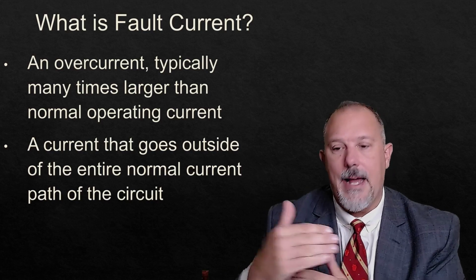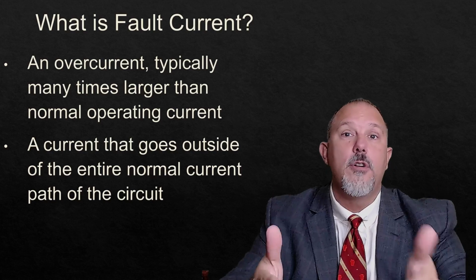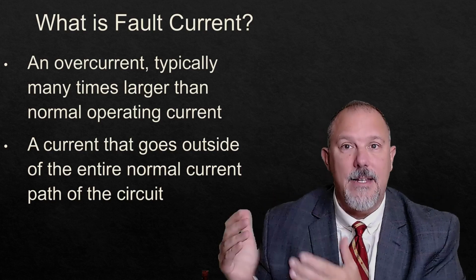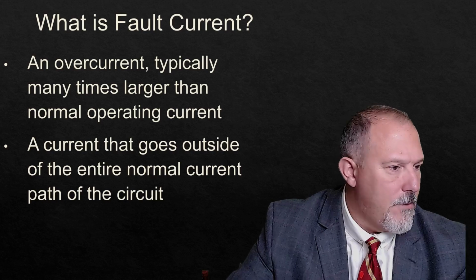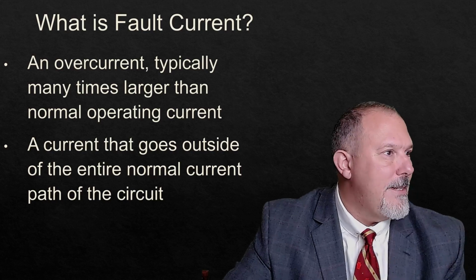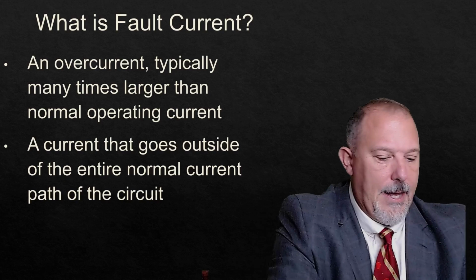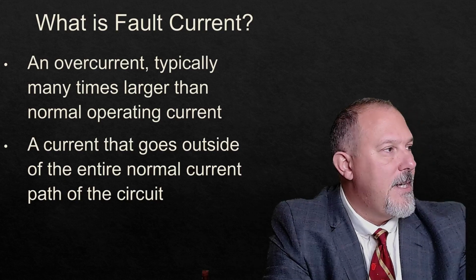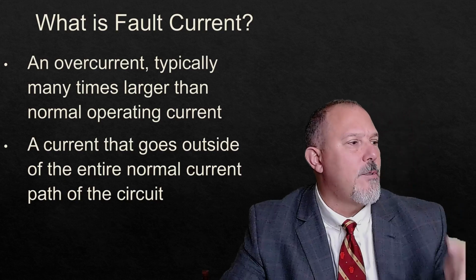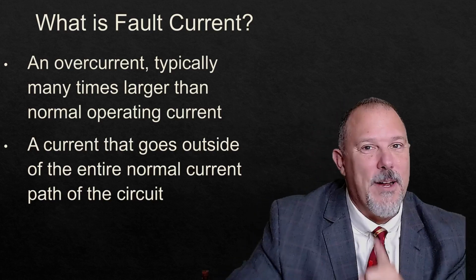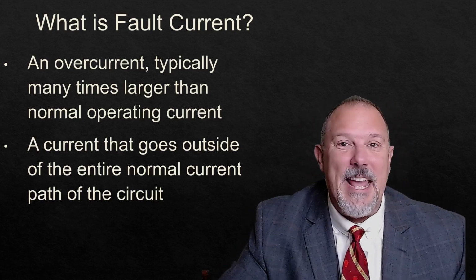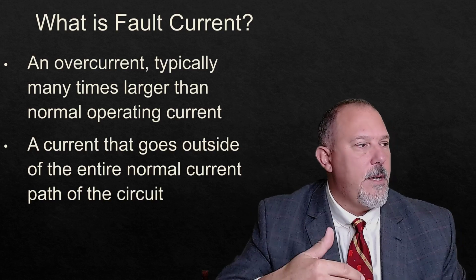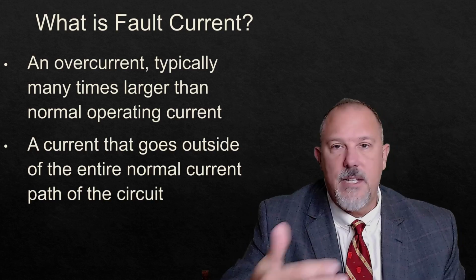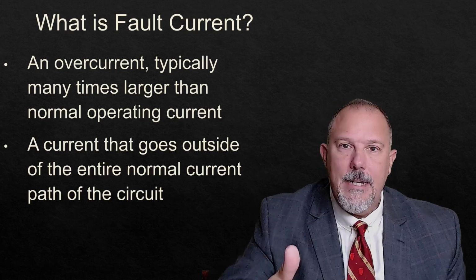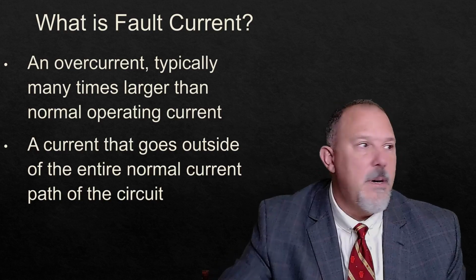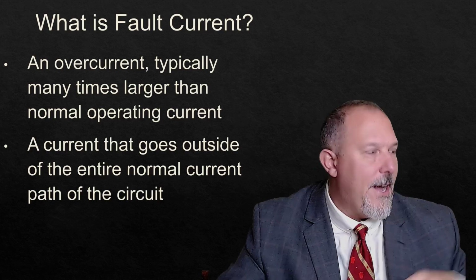you can download that document and understand how to test a breaker, or look at the NETA standards. What's the acronym? I want to make sure I get that right. NETA. NETA testing, the International Electrical Testing Association. I want to make sure I got the A correct. So NETA will give you some guidance. NEMA is the National Electrical Manufacturers Association.